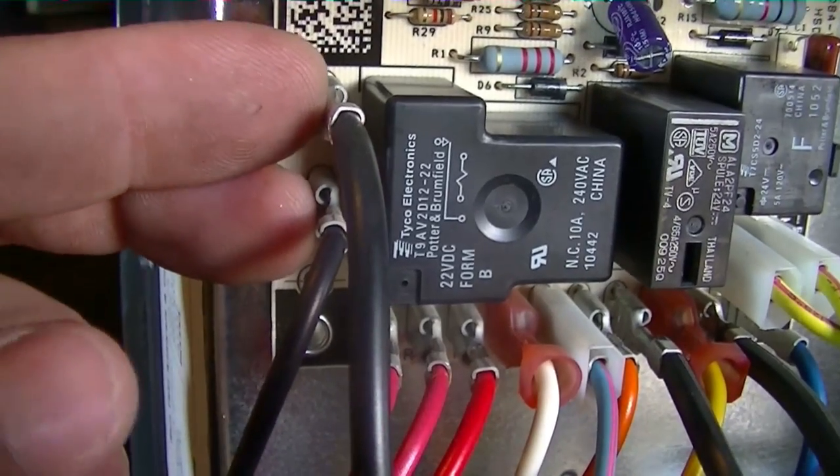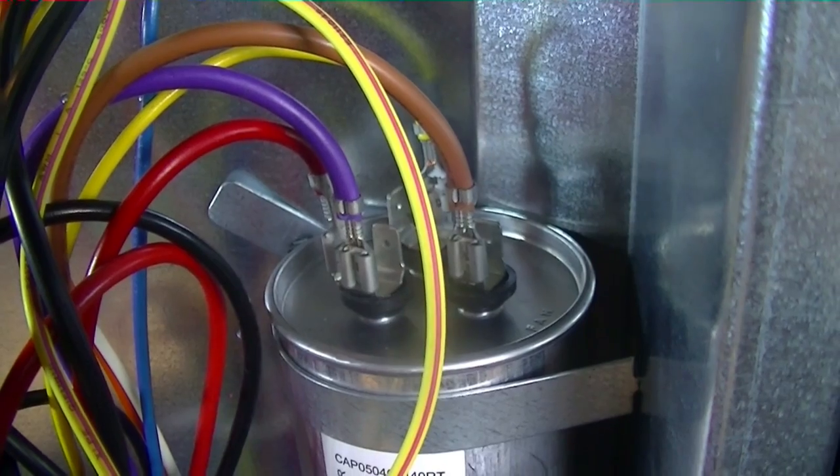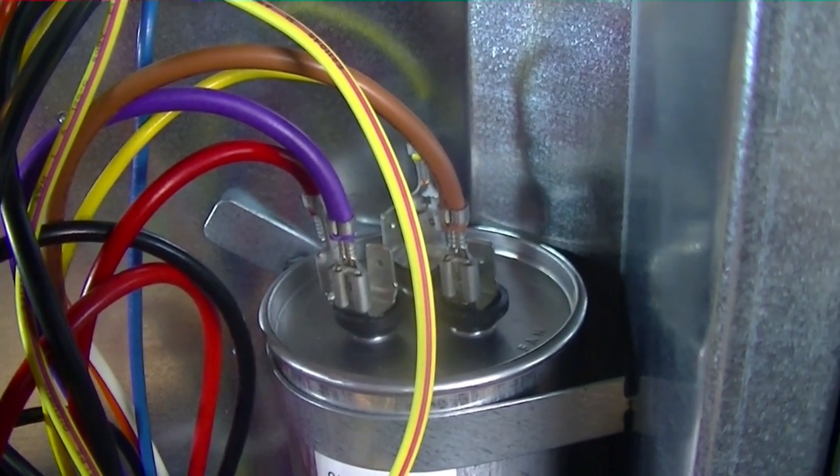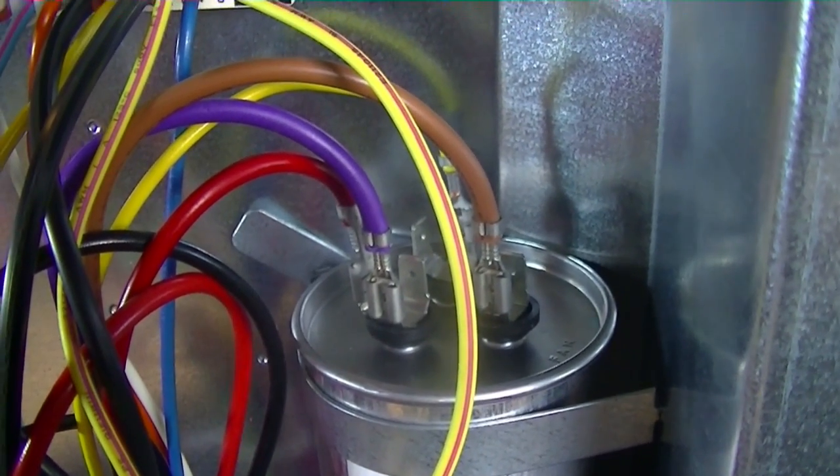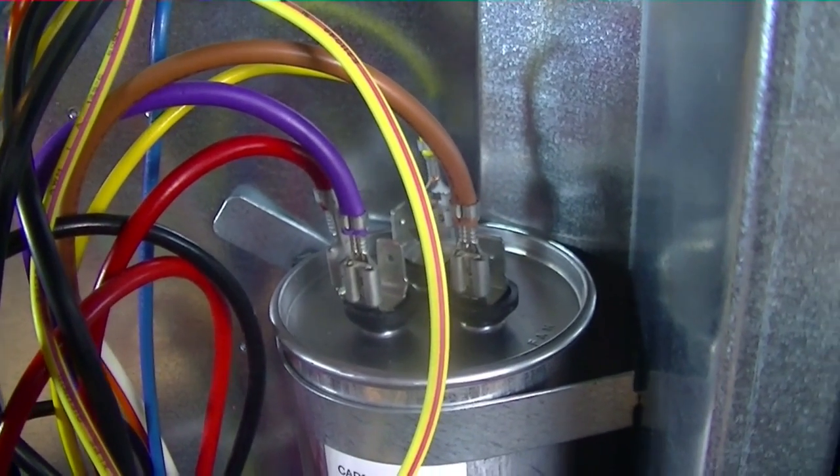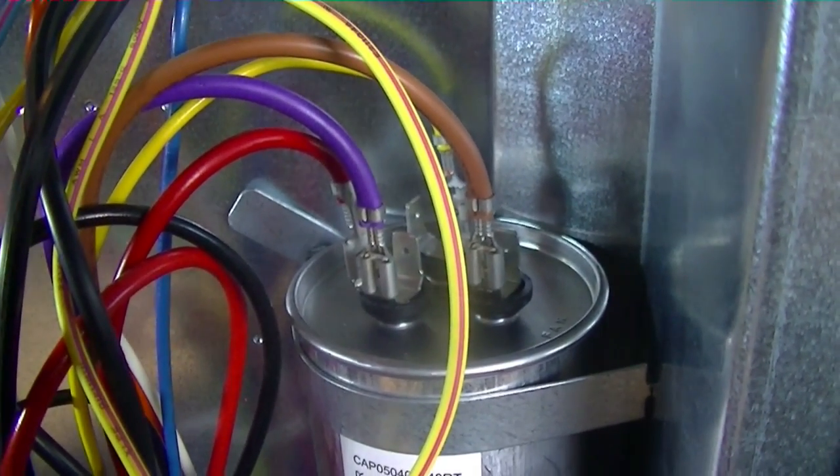One leg is going to the outdoor fan motor, one leg is going to the contactor. Both the purple, or run, from the fan motor, and the brown, or the start from the fan motor, go directly to the capacitor.